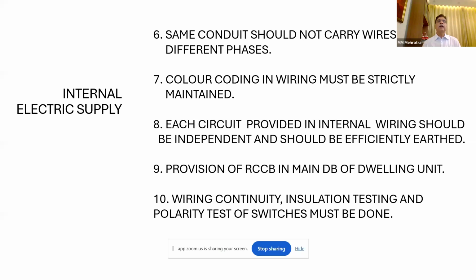Number two, the earthing wire will also be separate for each circuit. Each circuit means one set of wires: line, neutral, and earth. These three wires will run in one circuit. Now, if from one circuit I draw individual connections for lights, fans, and other things, they should be independent and efficiently earthed.